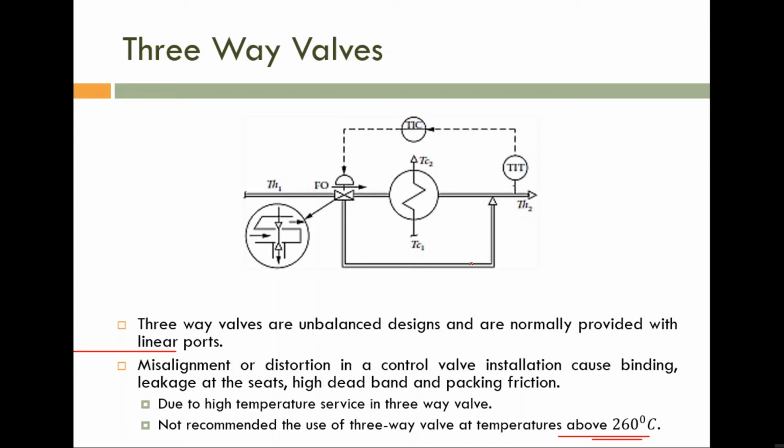That is the second problem. The third problem is not with respect to this control valve, it is with respect to the heat exchanger. Heat exchanger is a resistive device. Am I correct? So definitely it will provide some resistance to the flow of liquid through this heat exchanger. But the flow through this bypass line doesn't have any resistance, if you assume that the dynamic resistance is 0. All pipelines will provide some dynamic resistance, but for explanatory purposes, say the dynamic resistance is 0.